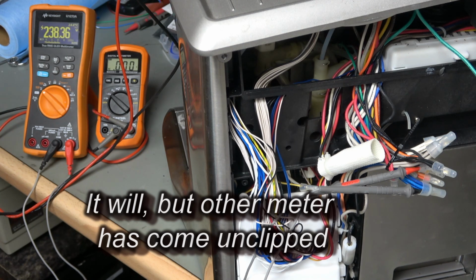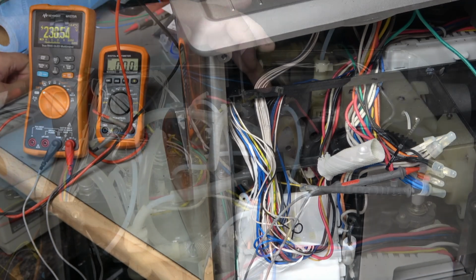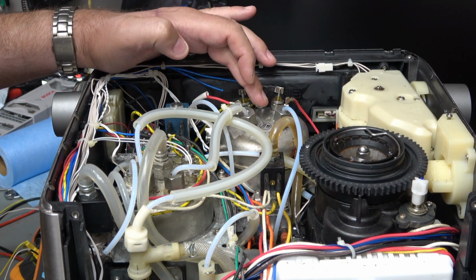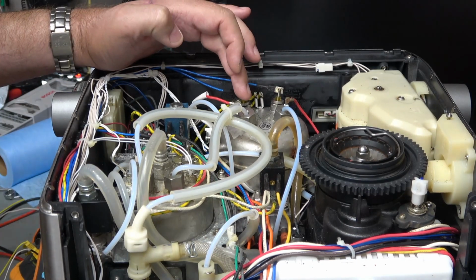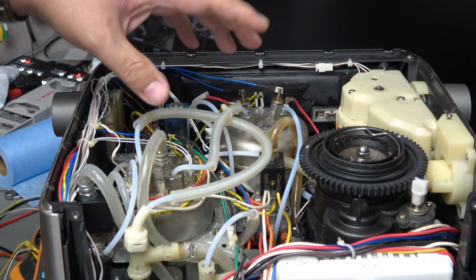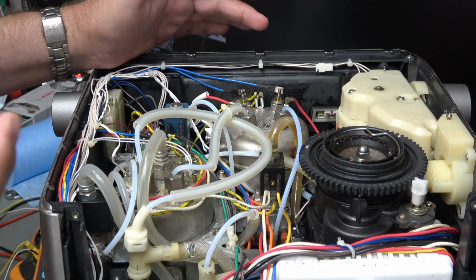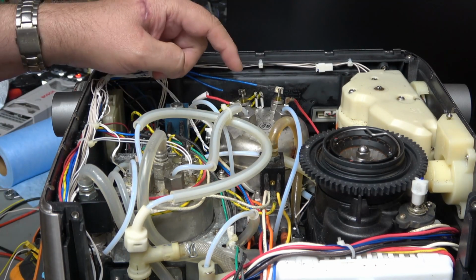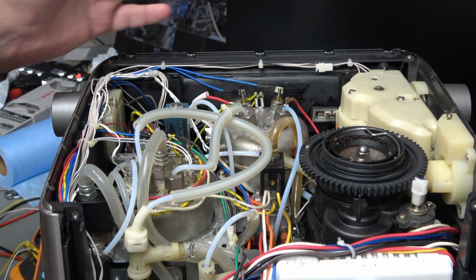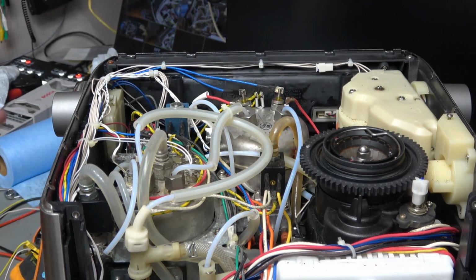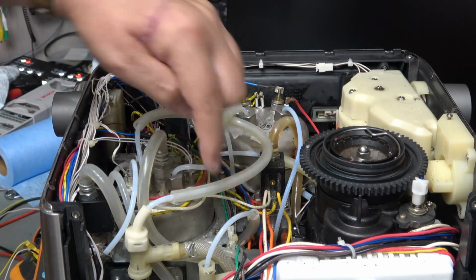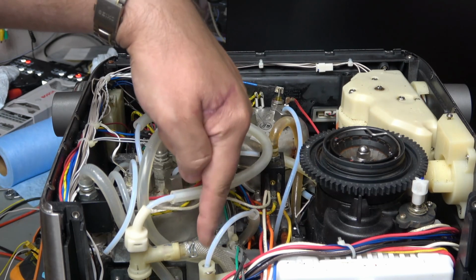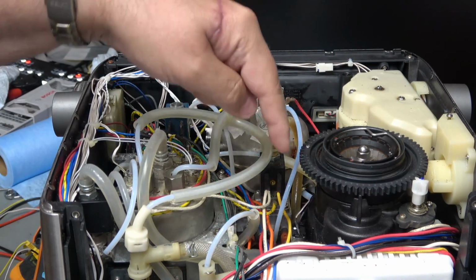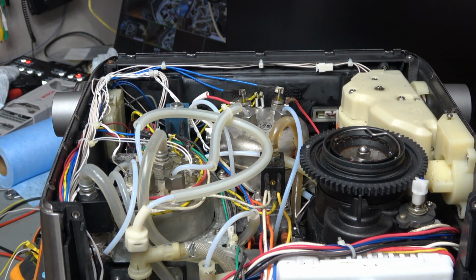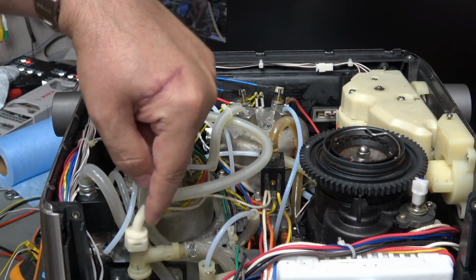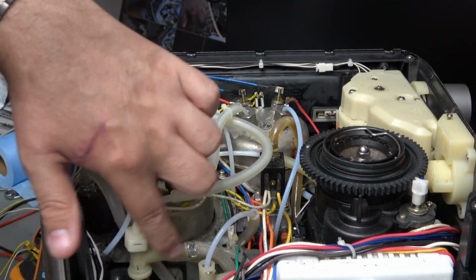Interesting, it's a steam boiler that's come on. It almost works - by that I mean it turns on, it comes up to temperature, it stops at the right temperature, the elements turn on and off appropriately, and it dispenses steam perfectly, and it dispenses hot water, but not with any pressure. And when I turn it off, what actually happens is I get a lot of back liquid coming through here and down this pipe just here, which is actually the overpressure pipe going back into the cold water tank.